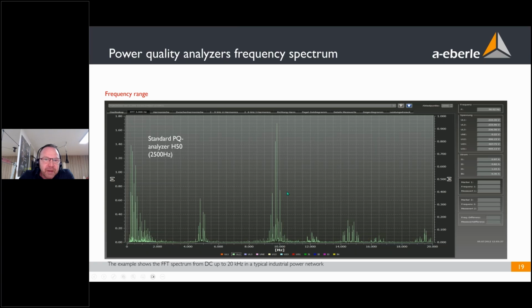So here we have a real measurement in the public grid, and here a lot of customers complained they have problems with electronic systems, like an electronic cooker that can't be switched on and off during normal working days. On the weekend it's okay. And a lot of people complain that they can hear some noise during the daytime, but not on the weekend. So there is some industry customer with some frequency converter who is causing interference to the network.